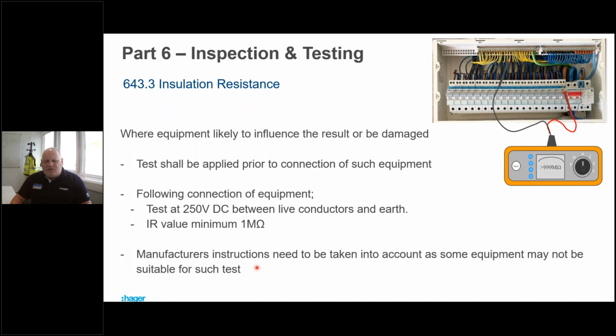Manufacturer's instructions, it's always good to read these. We test our equipment at 500 volts. Most of our equipment, we can put 500 volts through it without damaging it. There will be the odd item where we can't. It will always be written in the manufacturer's instructions, the voltage that you can put through these devices when you're doing your insulation resistance test.